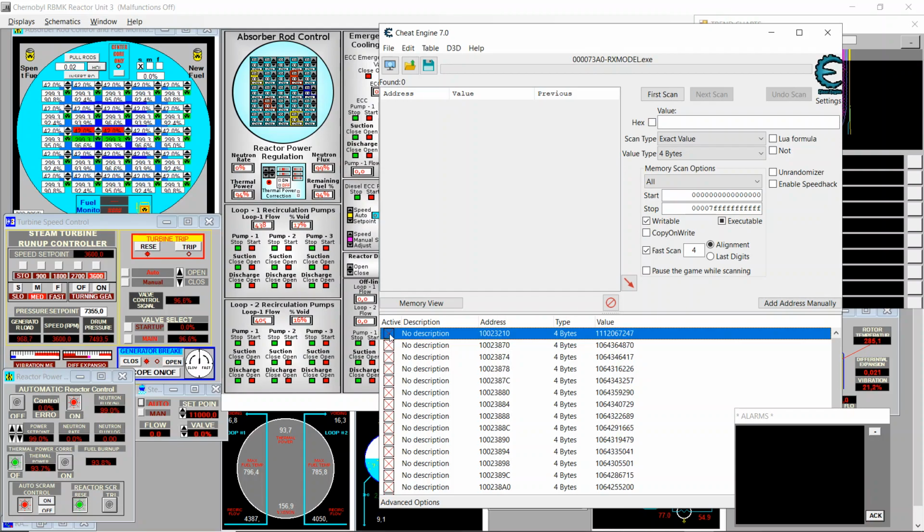When I deselect the xenon, because now the xenon concentration is fairly high, it's 156%, xenon is decreasing, you can see it now. The decimal point is decreasing as we look at it. It means the control rods are being inserted to compensate for this. That's why there is this discrepancy between power set point and neutron flux.